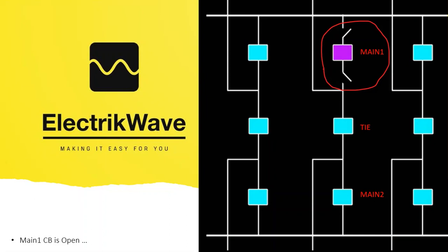However, relaying is somewhat more involved as the third breaker has to be responsive to troubles on either feeder in the correct sequence. Besides, each breaker has to be suitable for carrying the currents of 2 circuits to meet the requirements of various switching operations, which may in some cases increase the cost.